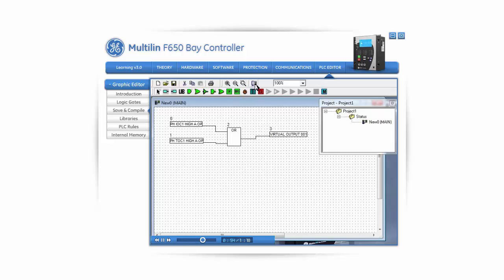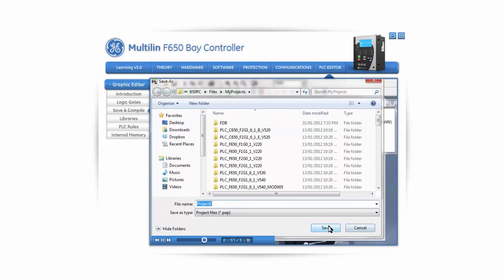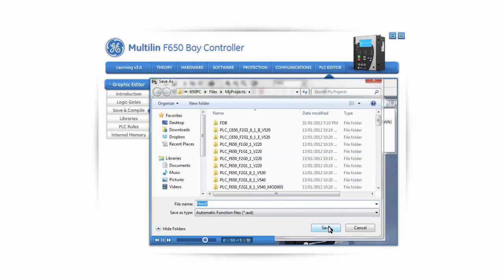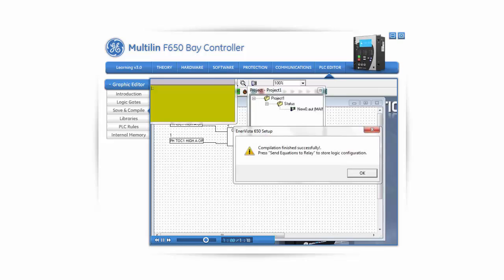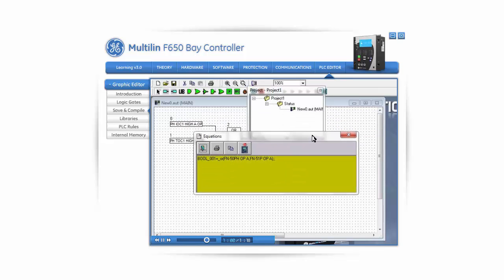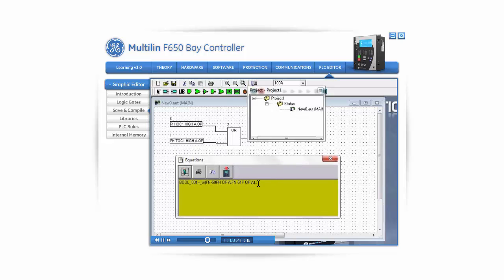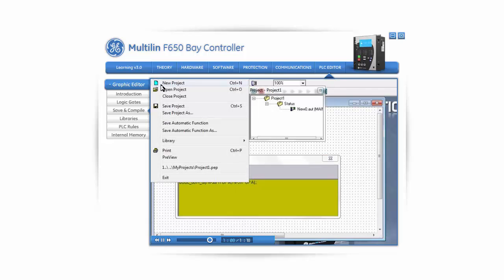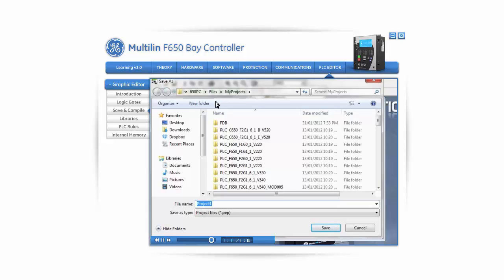After connecting all the flex operands together, we need to compile the graphical logic into equations that the F650 can understand. The compiler converts the graphical logic into equations that the relay can interpret. Click on the Compile icon of the PLC editor. The compiler will also check for any errors in the graphical logic, such as a missing connection between flex operands. After compilation is successful, you will be able to see the equations that the relay will interpret and implement. To upload the logic into the relay, click on Send Equations to Relay. To save your logic, go to File, Save Project As. Saving a project will automatically save all the files involved — including the project files, the automation files, and a database with the libraries. When sending the logic configuration from your PC to a relay, it is necessary to have all these files in one same folder.